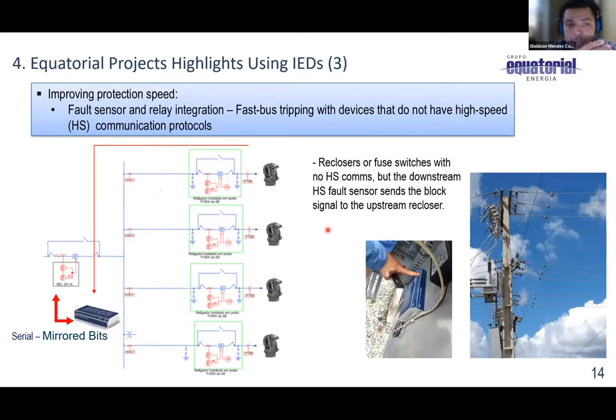Another project is for equipment that doesn't have high speed communication. We can use fault sensors and a relay to send the information to the recloser that a fault occurred in front of it. So it's going to do the same job as a fast bus trip scheme, but using different equipment. So using this, we avoid having to buy or change the equipment that we are using here.